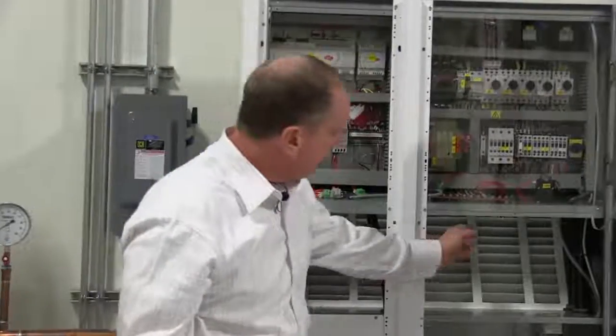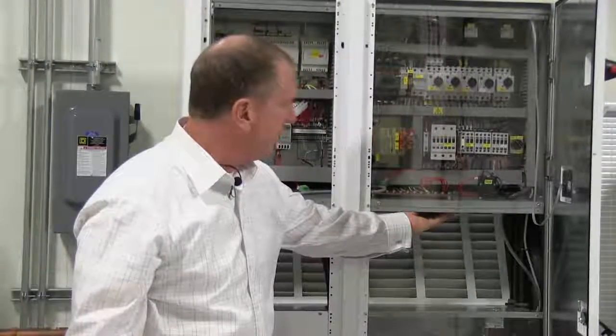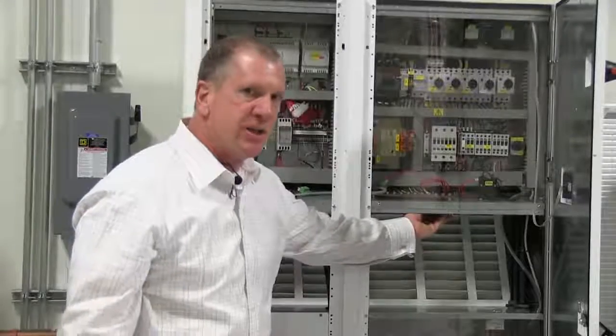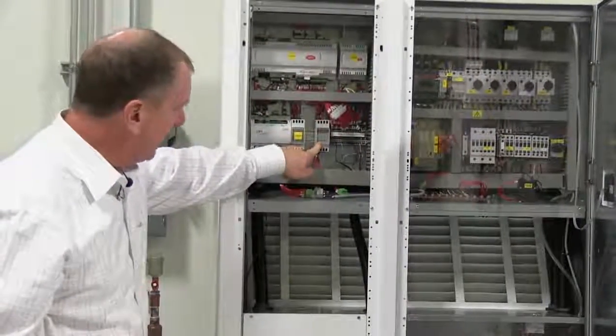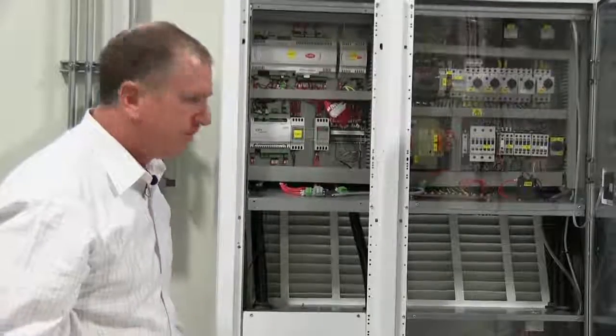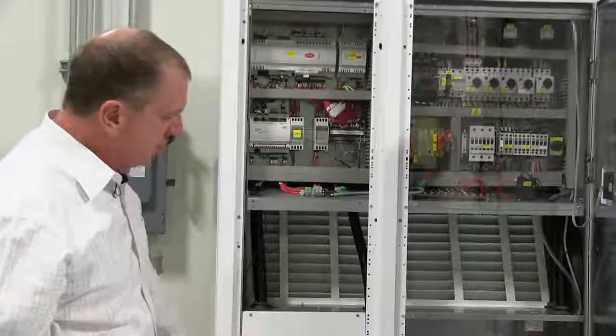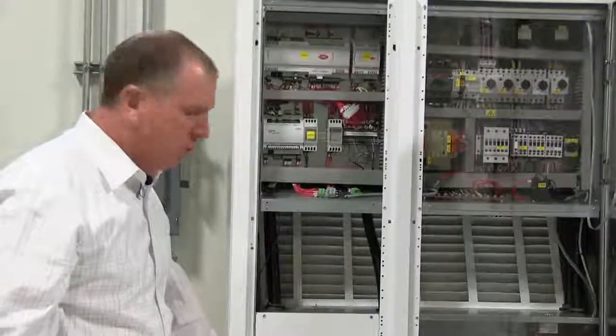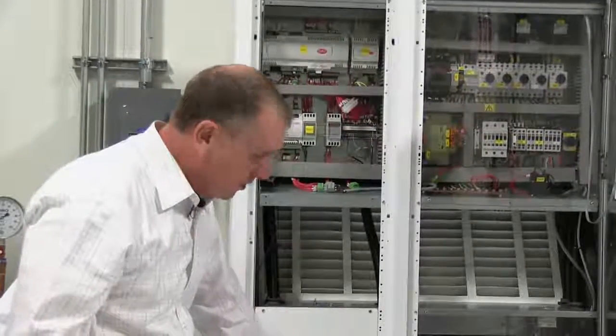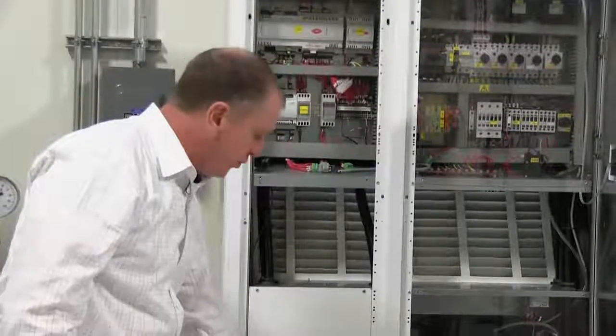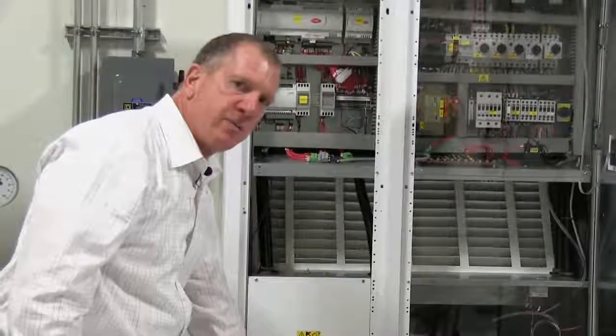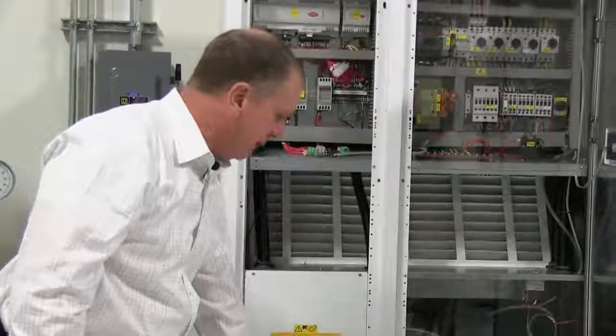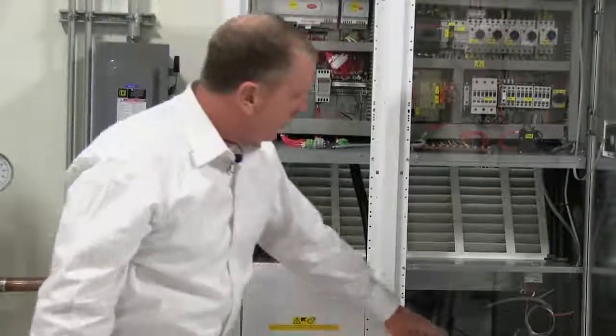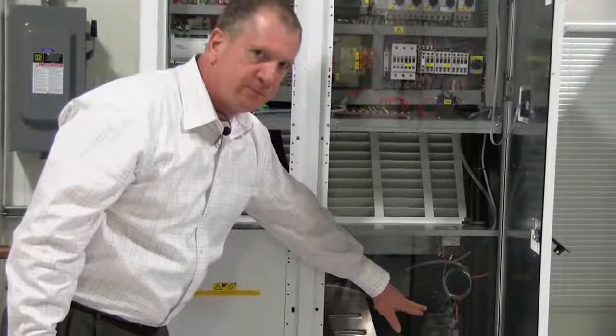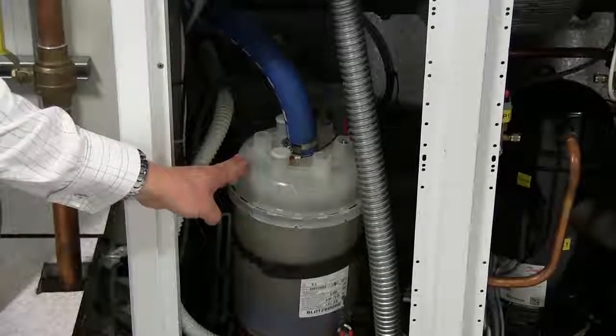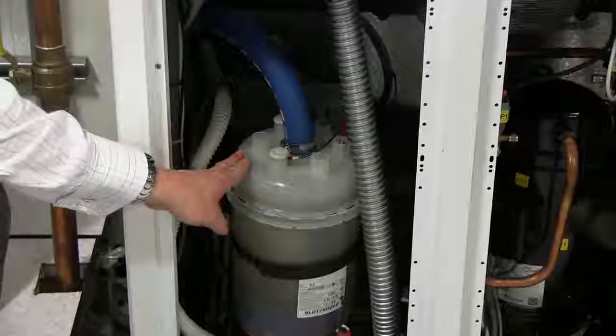For optional features on the unit, we have a smoke detector located on the underside of the electrical panel. There is a leak detector ribbon sensor that is wired up to here and surrounds the perimeter of the unit. This unit does not have a condensate pump, although if there were one, the drain would come from the coil to the humidifier, and then there would be a joint drain from the humidifier to the condensate pump. In this case, we're hard piped to a floor drain. Also, 3-phase electric reheat and steam canister humidification are options provided on this unit.